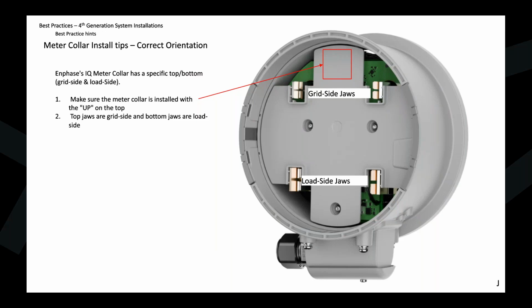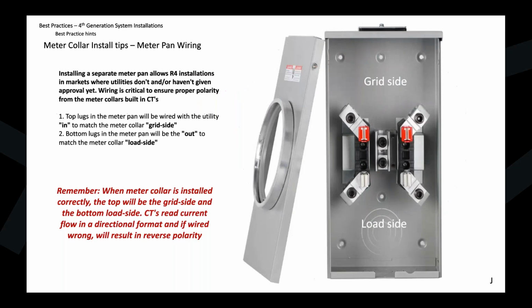This is going to ensure that we have the grid side jaws at the top and the load side jaws at the bottom. So as we've learned, we were talking about CTs earlier, this actually has the consumption CTs built in, and we want to make sure that we have phasing correctly, as well as polarity throughout the entire system. So again, this ensures that we have grid side at top, load side at bottom, and then that's also going to carry into an external meter pan.